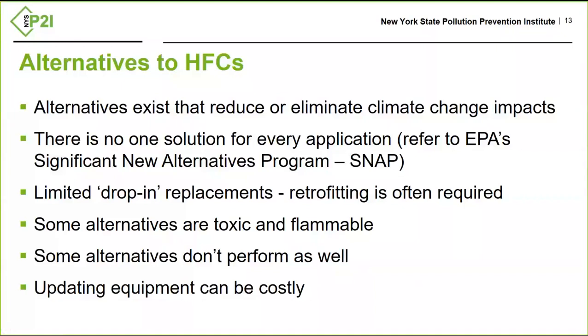Now there are some drop-in replacements, and what we mean by drop-in replacements is that you don't have to make any mechanical changes, you just have to remove the old refrigerant and put a new refrigerant in. So there are some drop-in replacements for certain current refrigerants or high GWP refrigerants. However, others require some fairly extensive equipment updates.